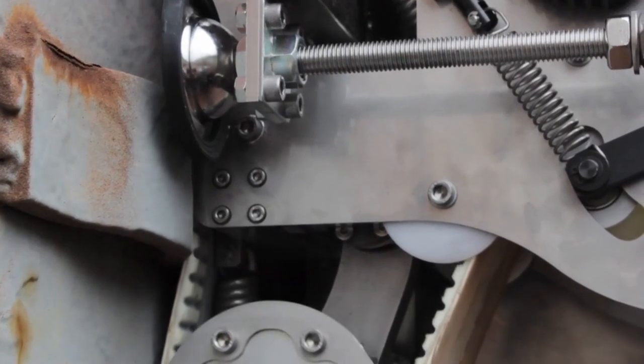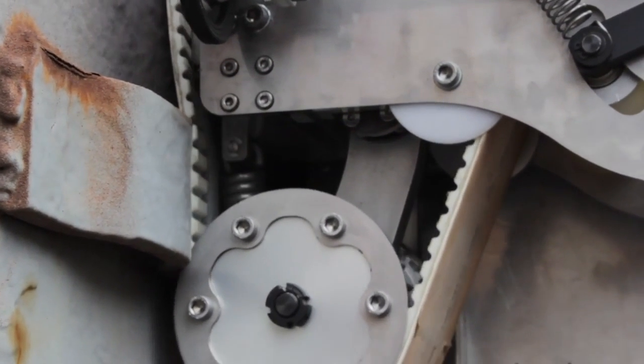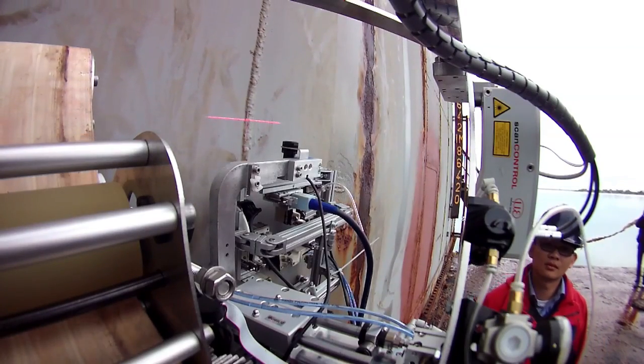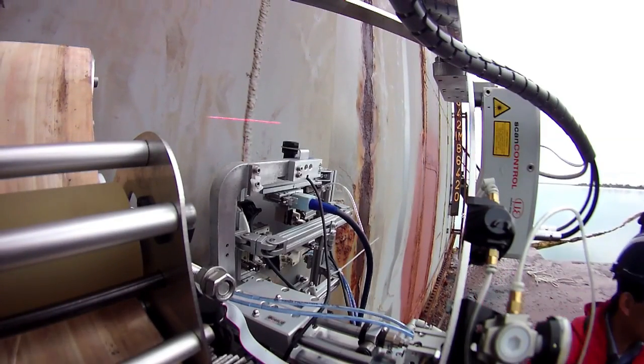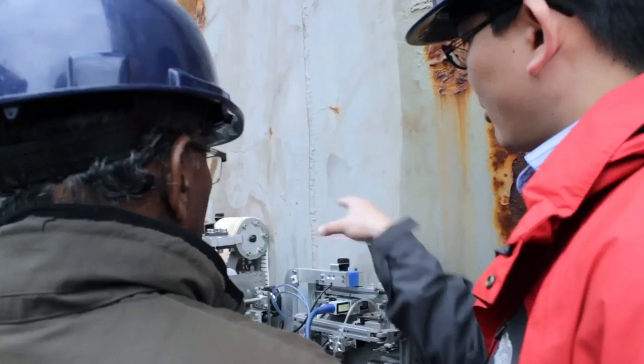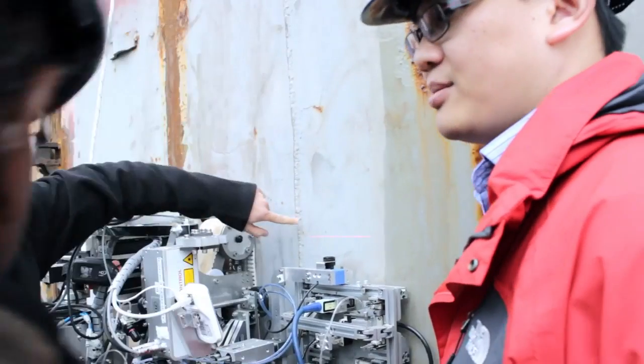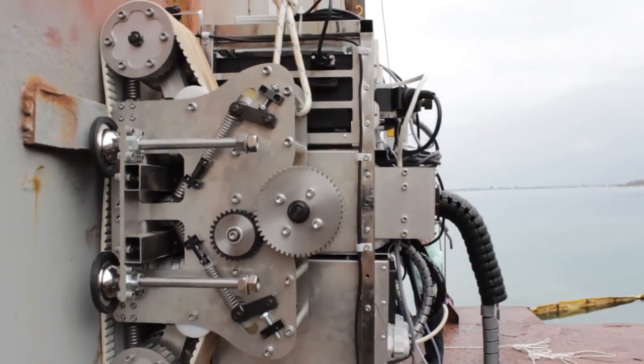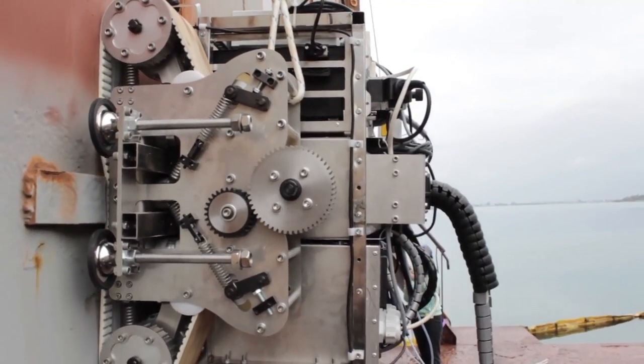By combining ultrasonic phased array, electromagnetic ACFM, and laser optical methods, this system is aimed at the detection and sizing of surface breaking and subsurface flaws. A laser-based tracking system and a self-control robot have been developed to allow the automatic inspection following the weld run.